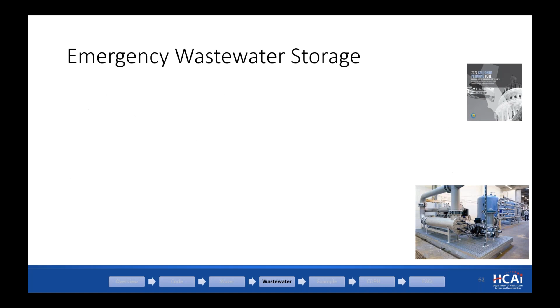So again, the California Plumbing Code, section 727, which is chapter 7, requires emergency sanitary drainage to support 72 hours of continued operation in the event of an emergency. Having a sewage overflow would probably be the last thing a facility would want to see. For new acute care hospital buildings, you're required to have on-site holding tanks to store sewage and liquid waste sufficient to operate essential hospital utilities and equipment in the acute care hospitals. For existing, the requirements are the same, but by January 1, 2030. Again, milestones are coming up, but the deadline is January 1, 2030.